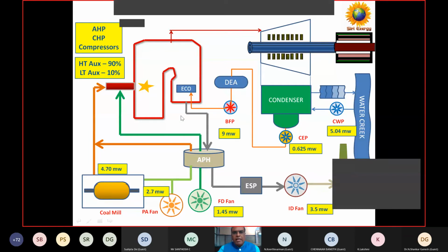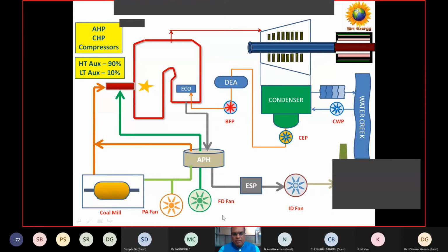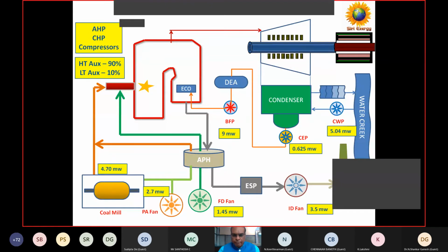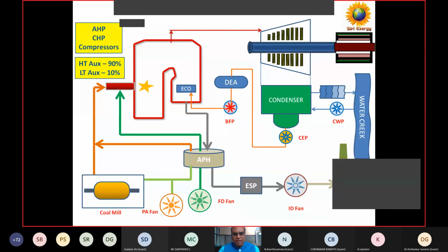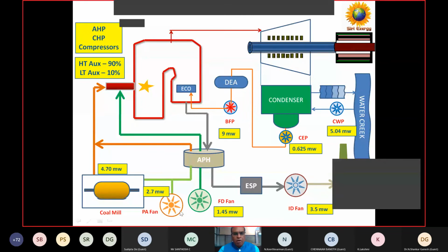Take a typical 210 megawatt power plant. You can see the load figures here. I'm not talking about the motor rating, but the actual power consumption on an hourly basis. The FD fan consumes 1.45 megawatt, and the PA fan consumes 2.7 megawatt.